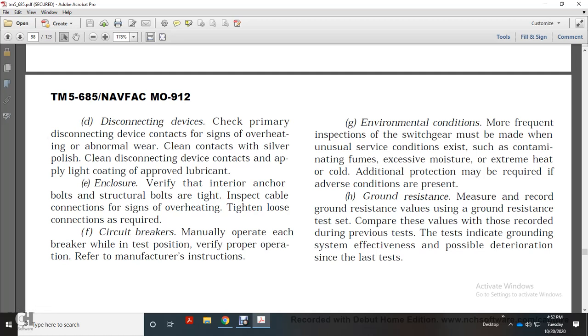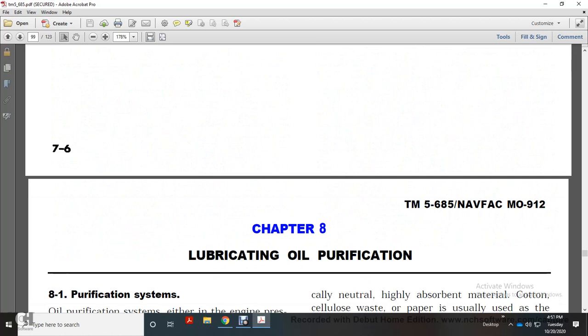Environmental conditions. More frequently, inspect switchgear when unusual conditions exist, such as contaminating fumes, excessive moisture, extreme heat, or cold. Additional protection may be required when adverse conditions are present. Ground resistance: measure and record ground resistance at the ground resistance test set. Compare the value with those recorded during previous tests to indicate the ground system effectiveness and possible deterioration since the last test. Alright, Chapter 8, Lubricating Oil Purification.